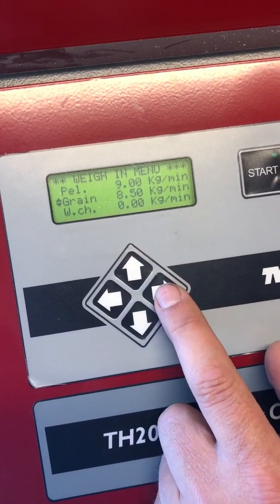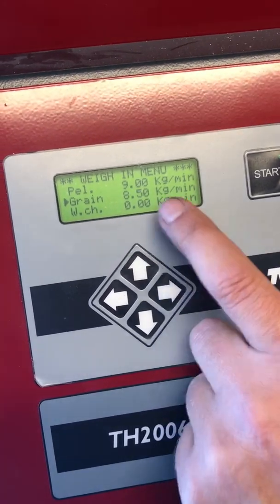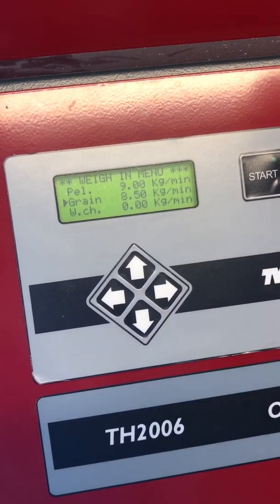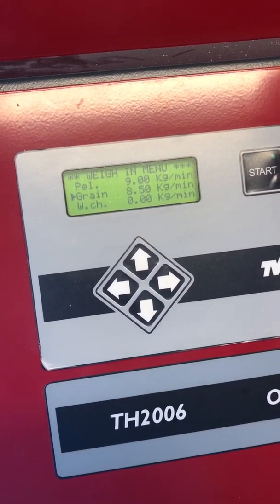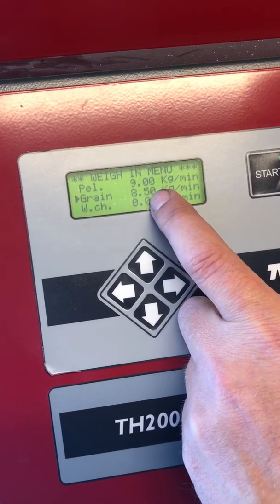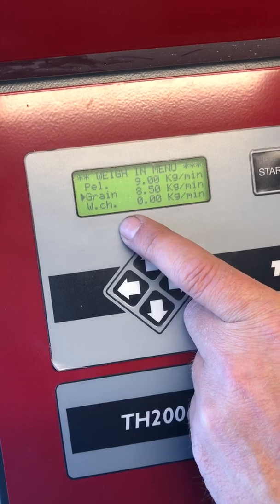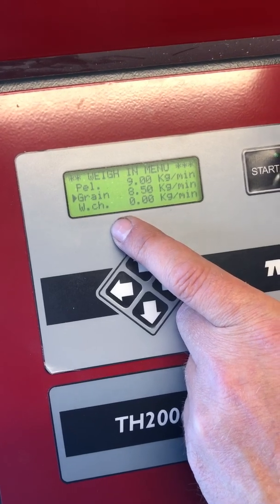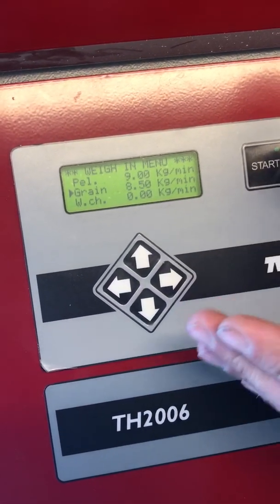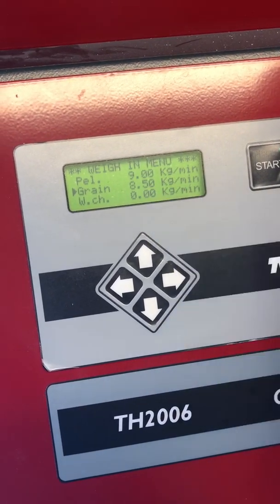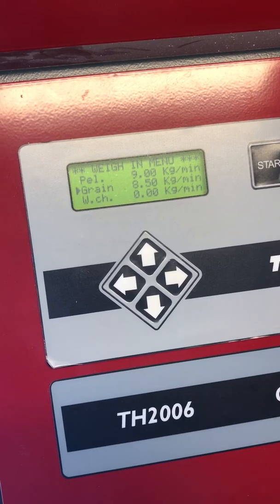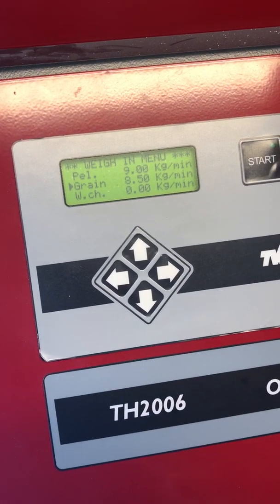Now that's adjusted. Remember if you have a bad fuel or whatever, if you want to give it less amount of fuel, you have to increase this — say instead of 8.5 kilo, go to 9.5 or 10 kilo. The more you tell here, the less it gives. We have put in 8.5 kilos, which is an average of what the boiler is using.